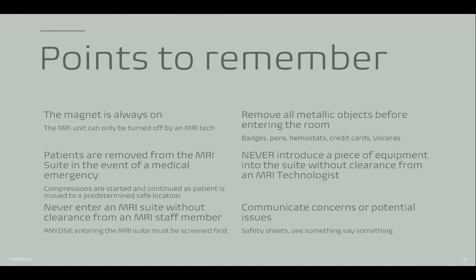Points to remember: the magnet is always on. The MRI unit can only be turned off by an MRI tech with a quench. Patients are removed from the MRI suite in the event of a medical emergency. Compressions are started and continued as the patient is moved to a predetermined safe location away from the MRI suite. Never enter an MRI suite without clearance from an MRI staff member. Anyone entering that suite must first be screened. Remove all metallic objects before entering the room.